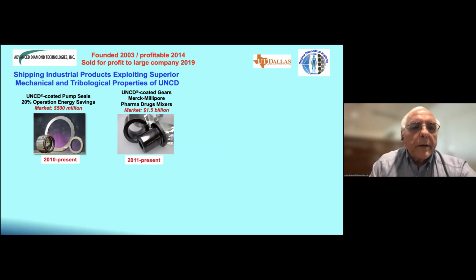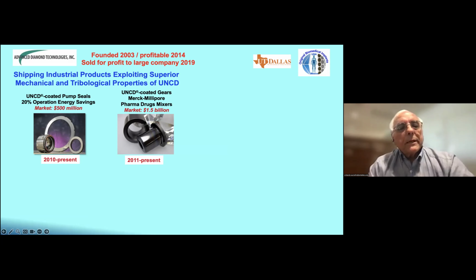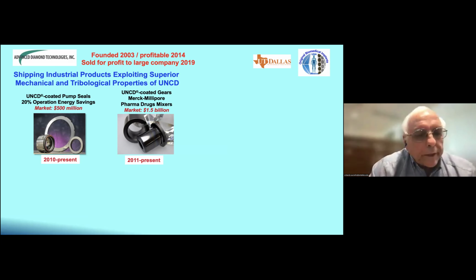Devices we put on the market with ADT: the first one, UNCD coated mechanical pump seals. Most mechanical pump seals in the world are silicon carbide seals with a friction coefficient of 0.5, and they have to be replaced in 4 or 5 years. With the UNCD coating, people now save up to 20% in the energy cost of running the pump because of the 0.02 friction coefficient, and they don't wear. So you can have UNCD coated silicon carbide seals on pumps for a long time.